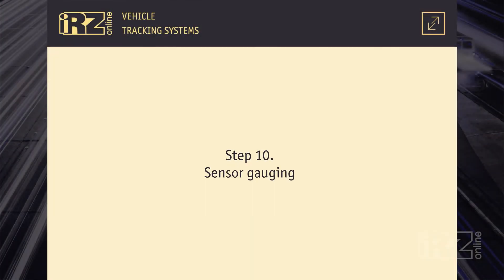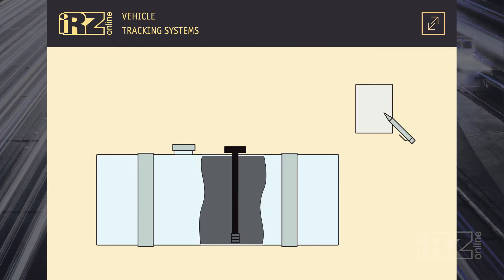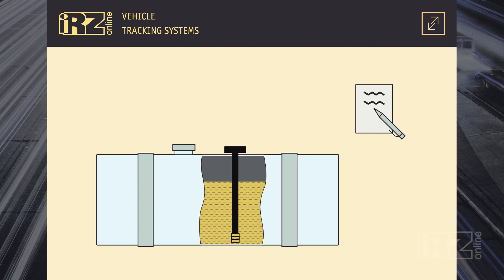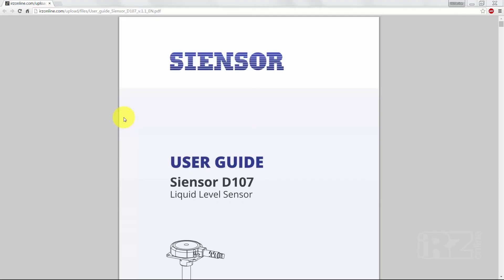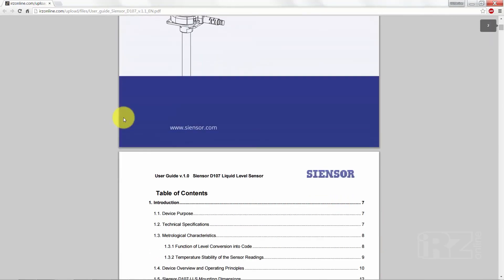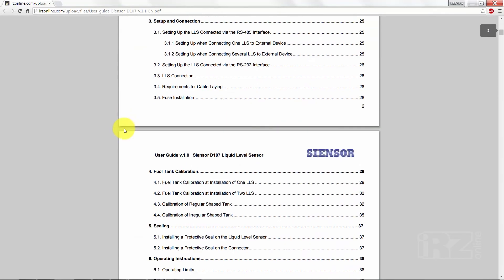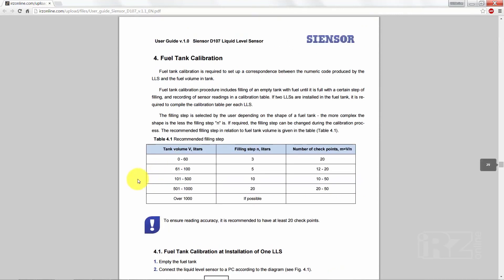The gauging is necessary to improve the accuracy of measuring of the fuel level in the tanks of an irregular shape in which it varies disproportionately. Fill fuel in the empty tank portion wise and fix the sensor responses. Thus calibration table is prepared. It is recommended to do at least 20 checkpoints. Select the fueling step by yourself. The more complex shape of the tank demands the smaller fueling step and more control points. Table of recommended fueling steps and the gauging of the tank are described in detail in the user's guide, section calibration of the fuel tank.